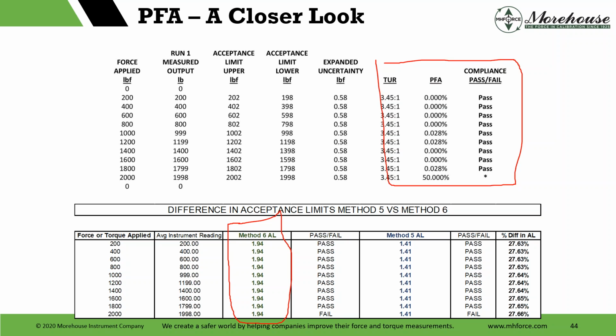So basically throughout, method 5 acceptance limit 1.41, method 6, 1.94. What that actually means is the acceptance limit is on both sides. So if I use method 6, as long as I read between 1998.06 and 2001.94, I should be good. I'm just going to subtract and add the 1.94 to 2000. So basically my limit is 1998.06 to 2001.94. Hopefully that makes sense.